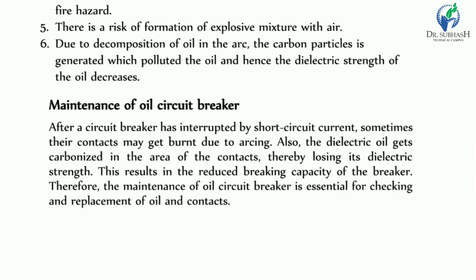After a circuit breaker interrupts a short circuit current, contacts may get burnt during arcing. The dielectric oil gets carbonized in the area of contacts, thereby losing its dielectric strength. This results in reduced breaking capacity of the breaker. Therefore, maintenance of the oil circuit breaker is essential for checking and replacement of oil and contacts.